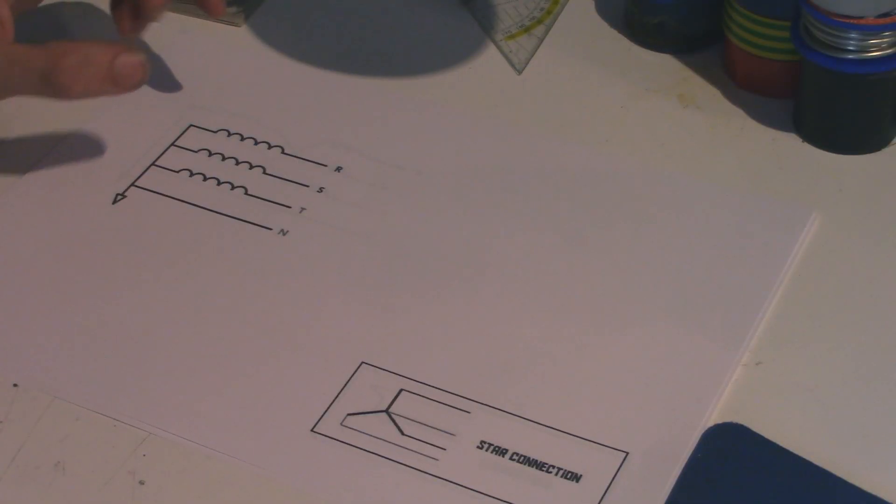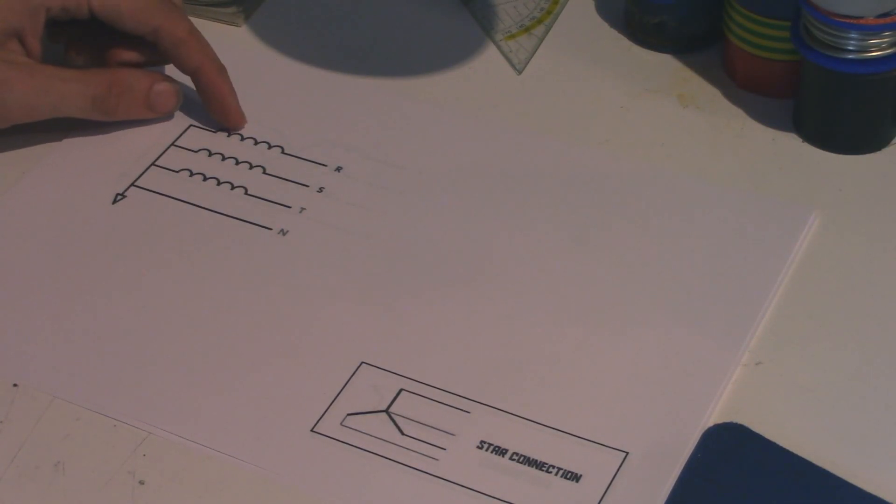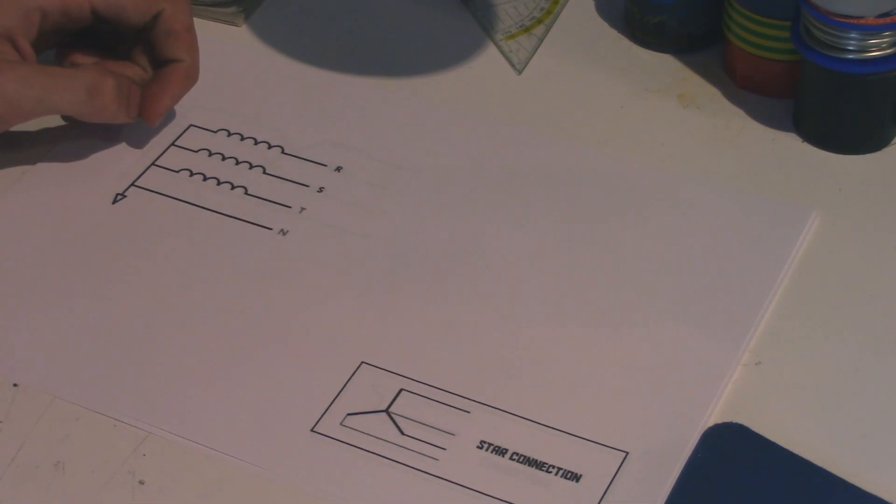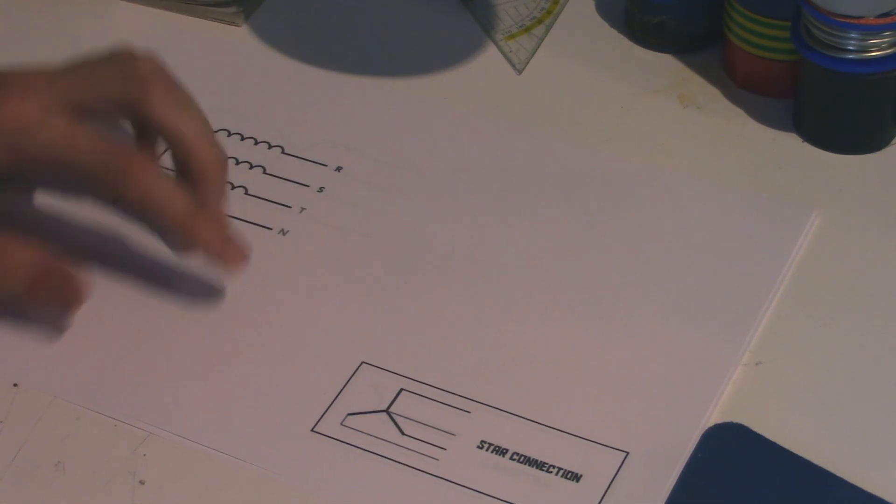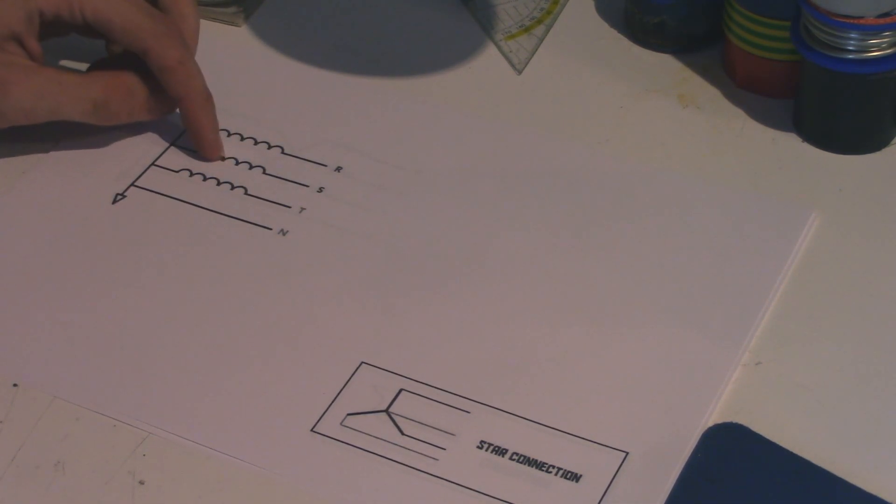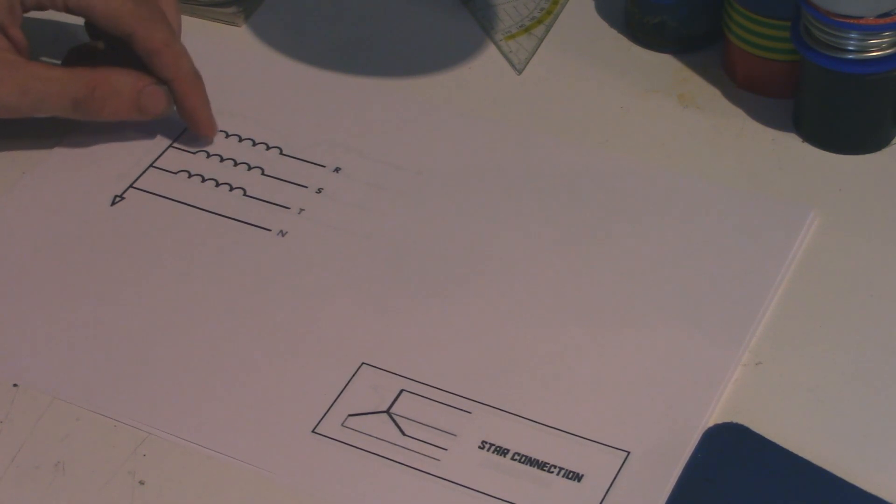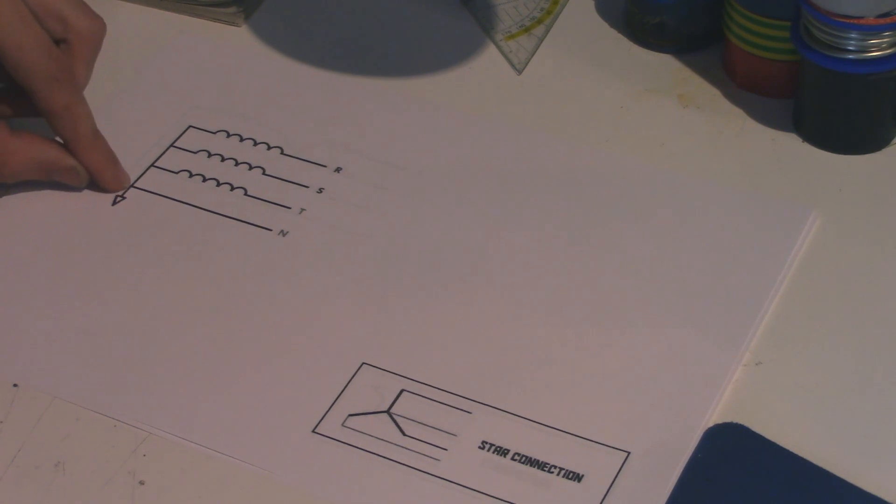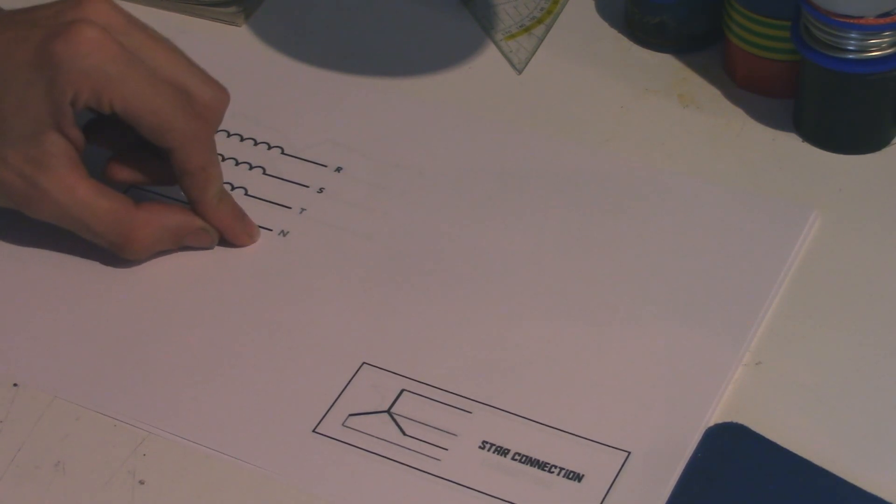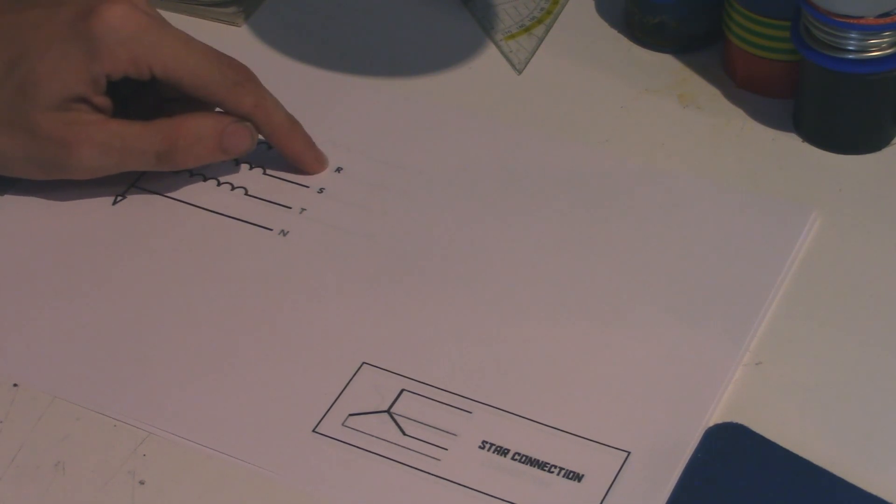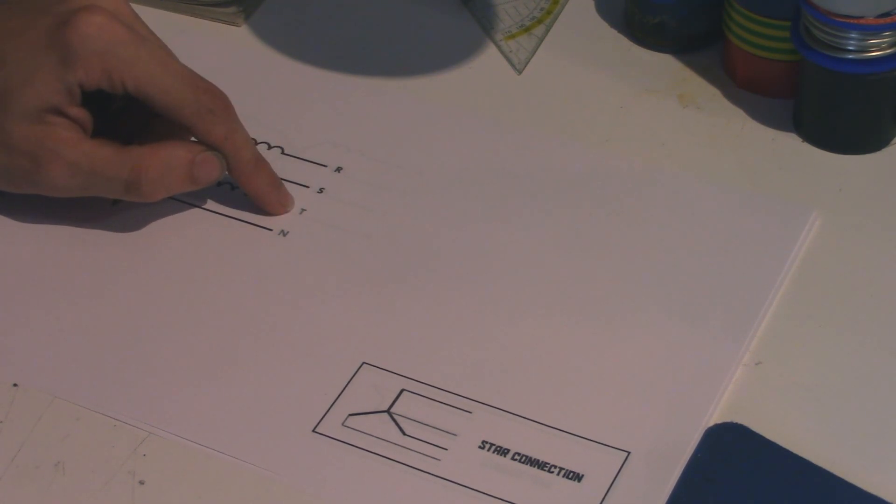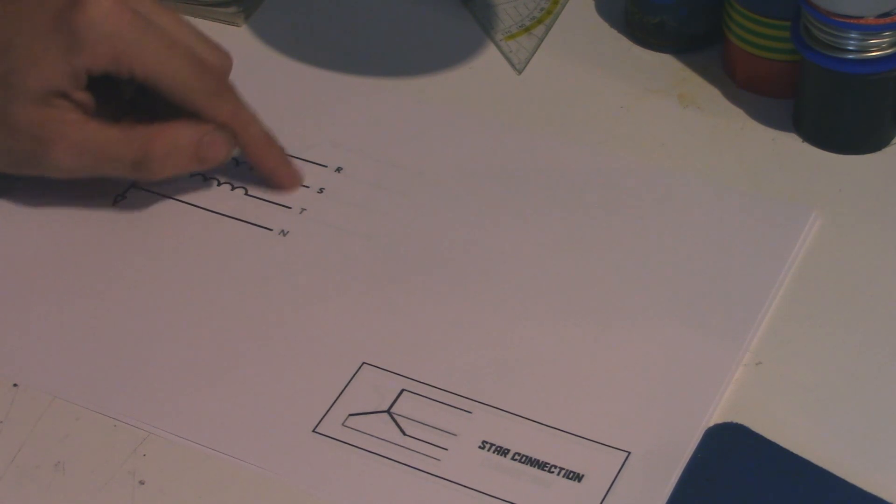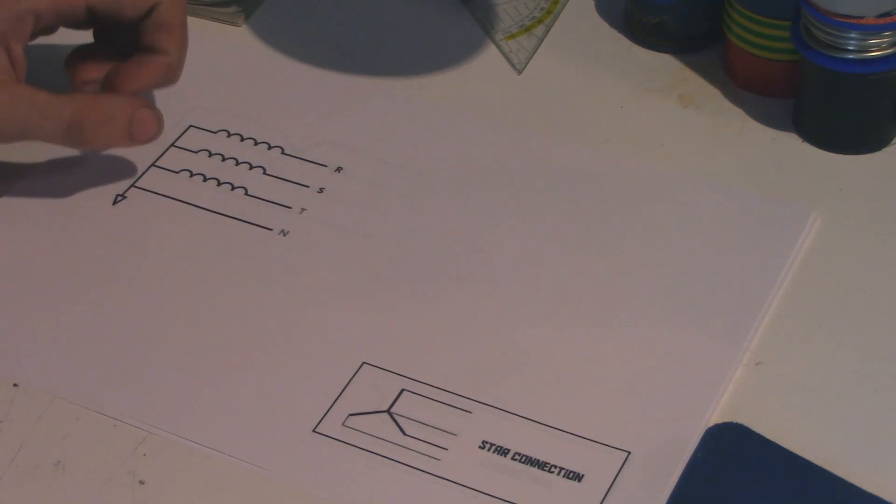So this is also known as a secondary. In this particular transformer, the secondary side is using a star connection. So what this means is that we've got three coils, one for each phase, and these coils are connected to one central point, which we connect to the ground, and that's also a neutral wire. And so at the output of this transformer, we have three phases, R, S, and T, and a neutral wire, and these then go to the customer's houses.